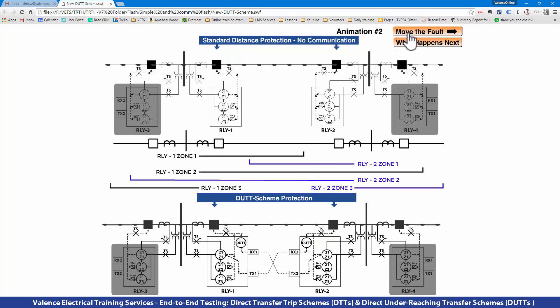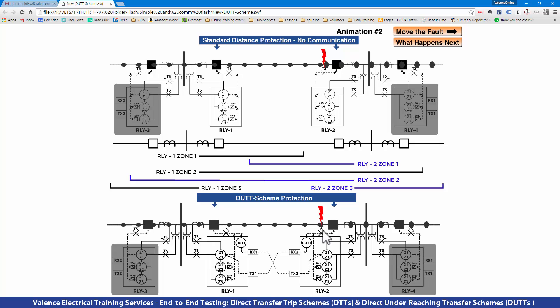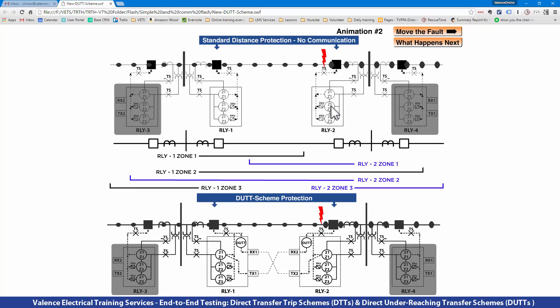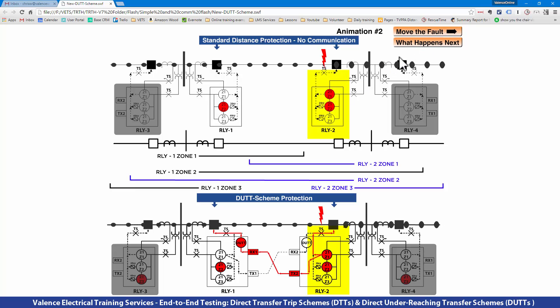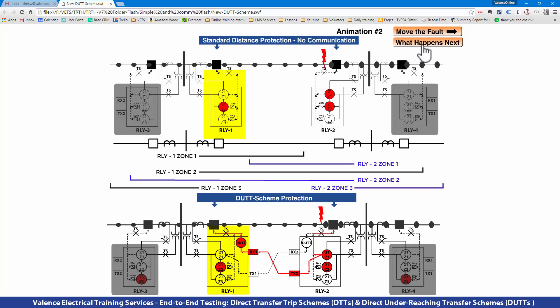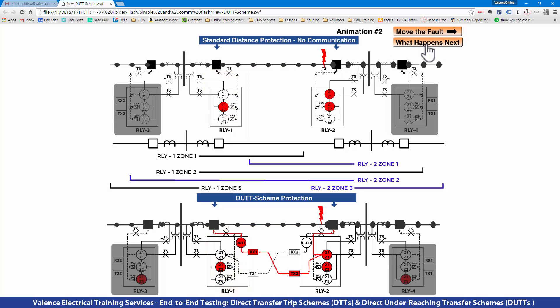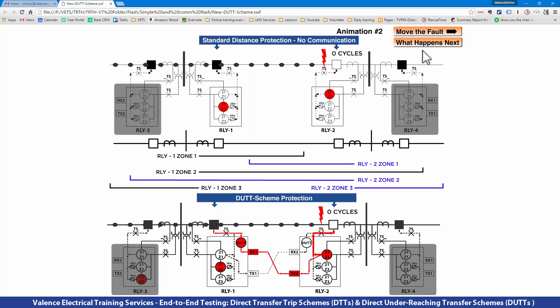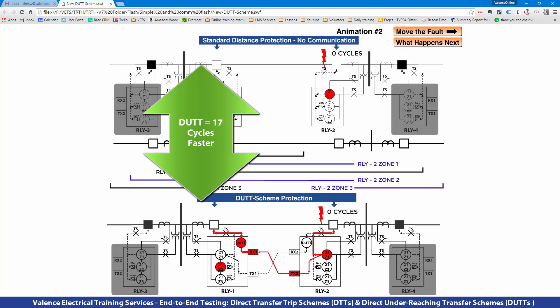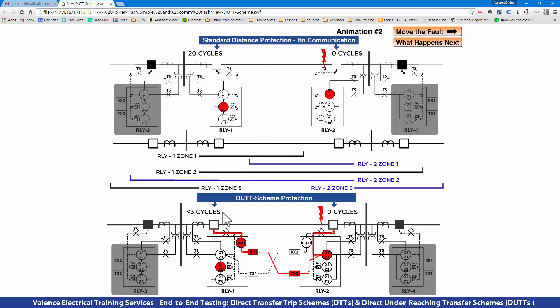If I move the fault to the other side, the fault is now close to Relay 2, and the opposite happens. Relay 2 sees Zone 1 and Zone 2. Relay 1 sees Zone 2, and the breaker connected to Relay 2 opens instantaneously. Then we have that 20-cycle delay before the breaker on Relay 1 opens.